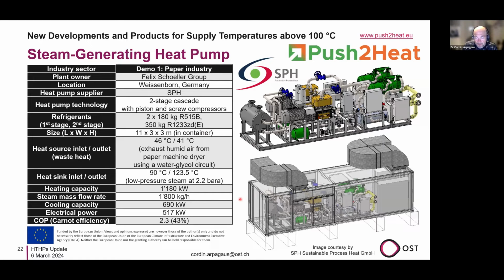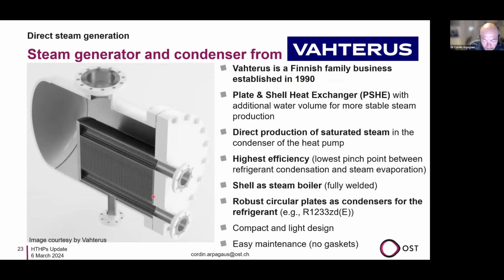The application is drying. It's a paper factory using the exhaust air from the dryer as a heat source to generate low pressure steam. So you see here the temperature lift. The humid exhaust air first goes through a heat exchanger that produces a water glycol circuit, which then goes into the heat pump as a source, and it generates steam. The COP is 2.3, with a capacity of 1180 kilowatt, which is 1800 kilograms of steam per hour. So another very interesting application.